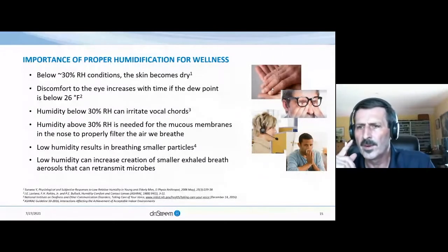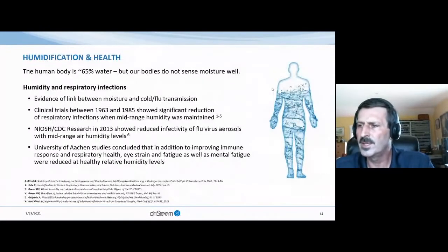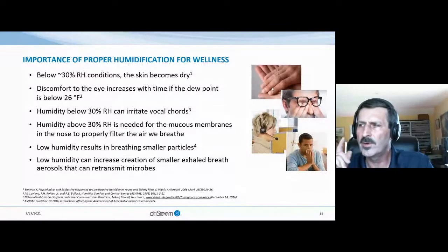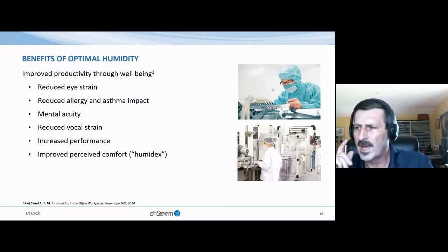Building on the notion of discomfort in low humidity environments, it dries out the human body. For example, skin dries out and eye dryness leads to irritation. Particles in the air also dry out, causing them to shrink in size. Our mucous membranes in our nose and throat dry out, reducing our ability to filter these particles. Having smaller particles and less ability to filter through those mucous membranes contributes to the increased infectivity of cold and flu viruses. In addition to the consequences of low relative humidity, there are several benefits to having the right relative humidity. This list includes several pertaining to comfort, and whilst more difficult to quantify, they also influence how people feel within a space and indirectly productivity.